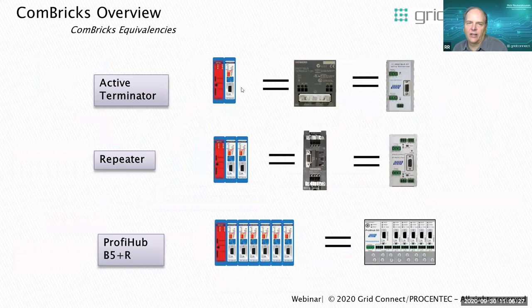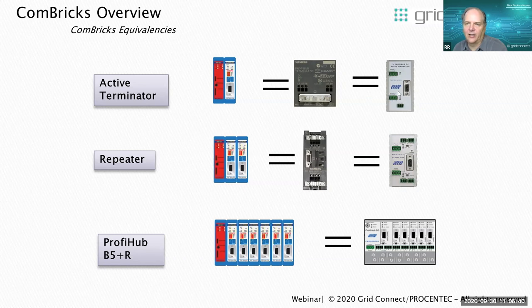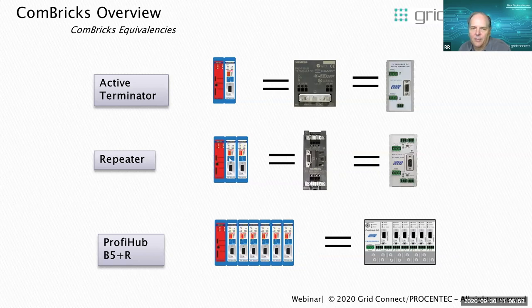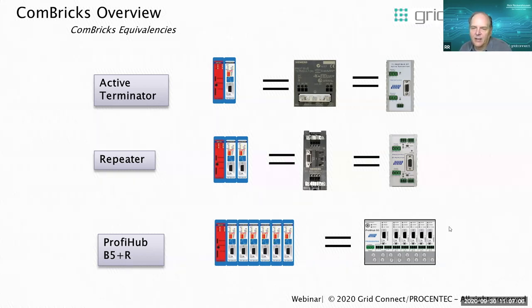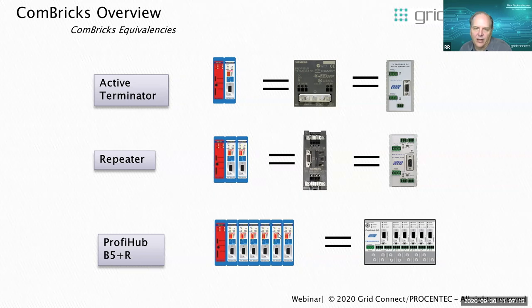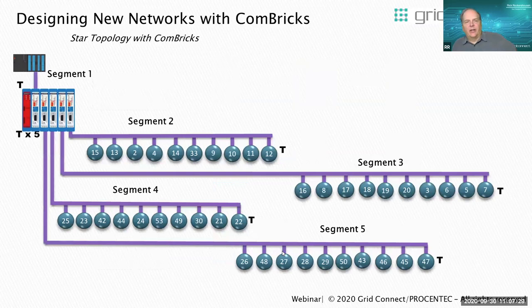For fiber, Combricks supports star, tree, line, and ring topologies, on both multimode and single-mode fiber — single mode giving greater distances. In terms of equivalencies, if you have an active terminator in your network, you can replace it with a single head station and a single module. To replace a standard repeater, you need two segment modules — one equivalent to the top of the repeater and one to the bottom. To replace a ProfiHub B5R (five channels plus main, six total), you need six segment modules on your Combricks.